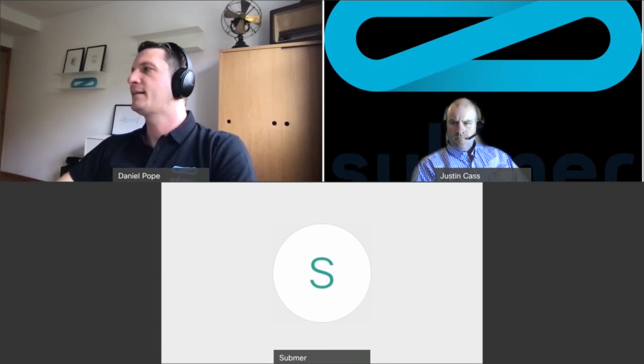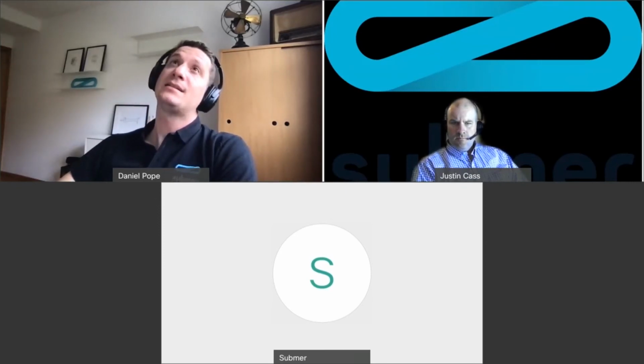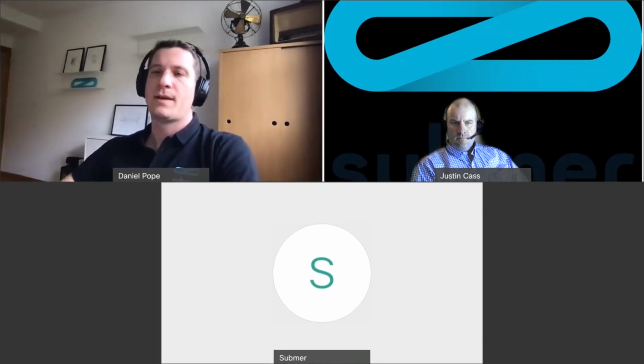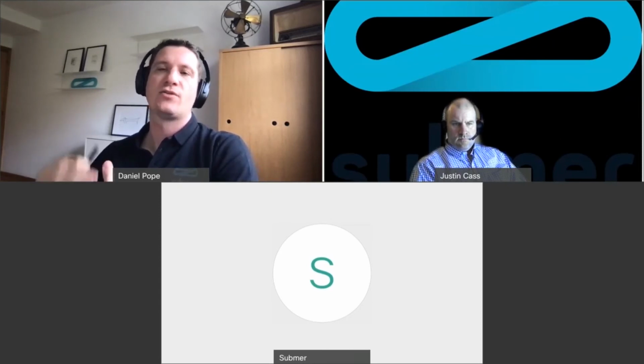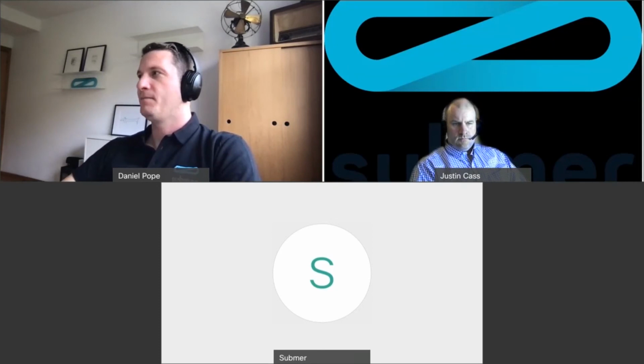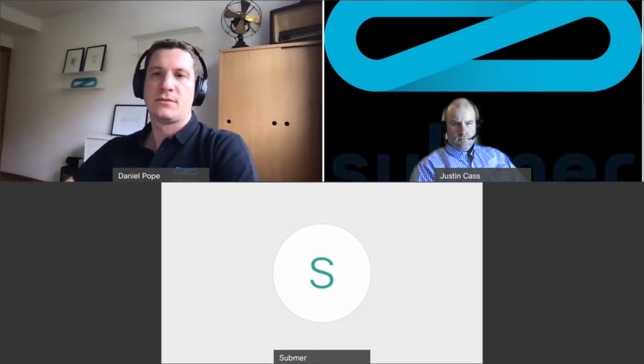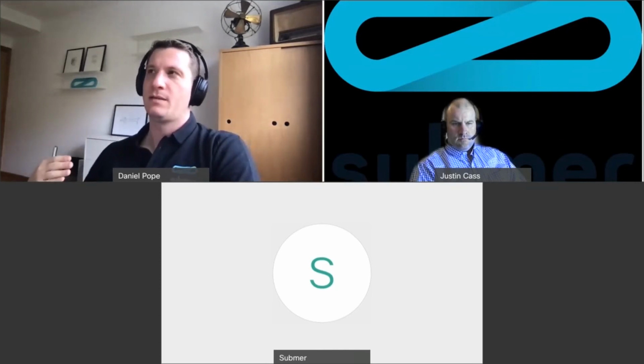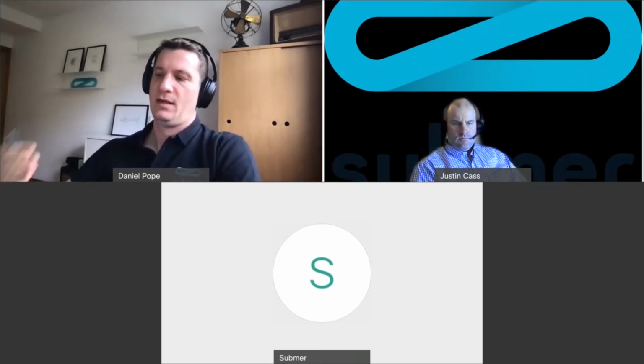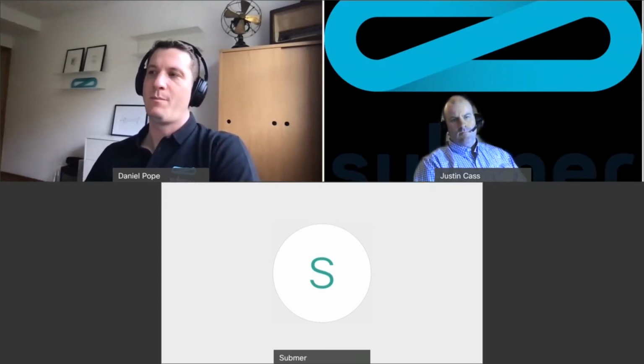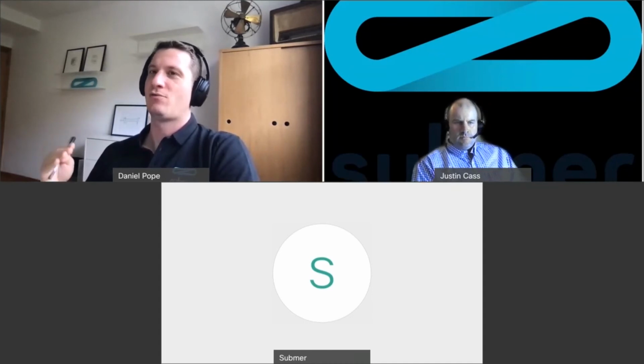What am I missing? What is the limiting factor for 800 kilowatts? The limiting factor is that today without doing anything special, the SmartPod XL platform supports 100 kilowatts per immersion tank with very warm water temperatures. So if the water temperature is colder, those 100 kilowatts can go higher. It's how we've sized the system today, to say the truth, because although single-phase immersion cooling allows us to achieve much more, until the IT equipment doesn't catch up, and no one's seen a 100 kilowatt rack yet. I'm hoping we see one soon.